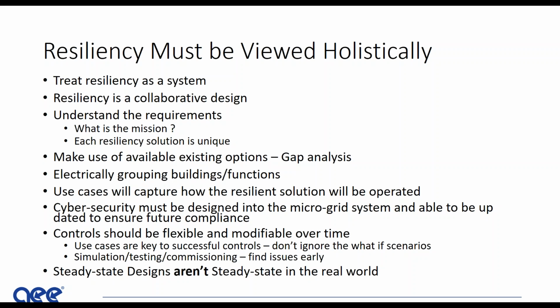The philosophy shouldn't change. You commission at the lowest possible subsystem level you can, whether that's a control point, a repeater system, an actuator opening and closing, or how the closed loop system reacts. This all relates back to the same type of system, whether resiliency is the particular question. The process should be the same, or very nearly the same, for any building you put together. You just have multiple floors or multiple rooms.